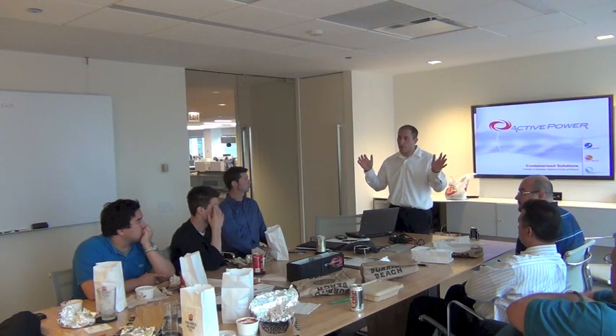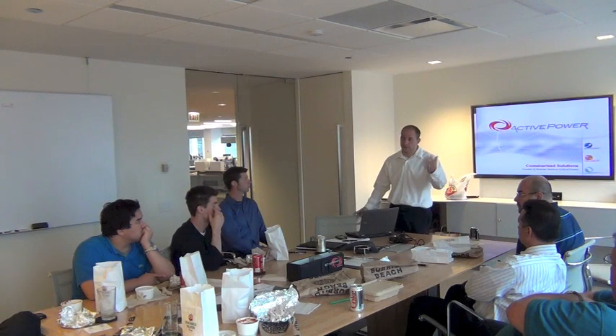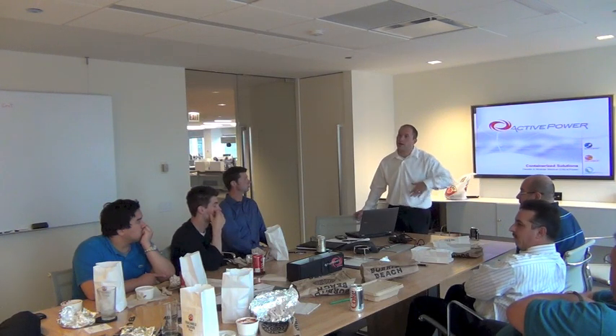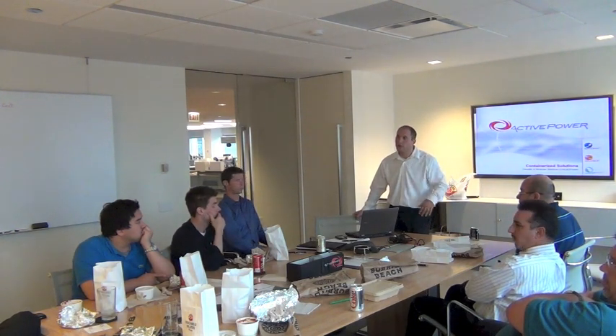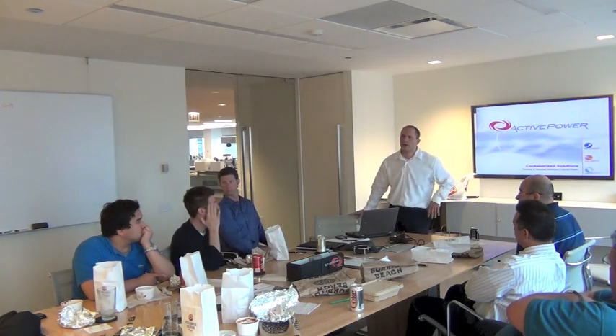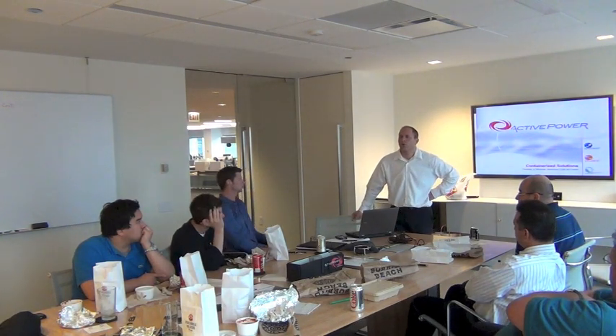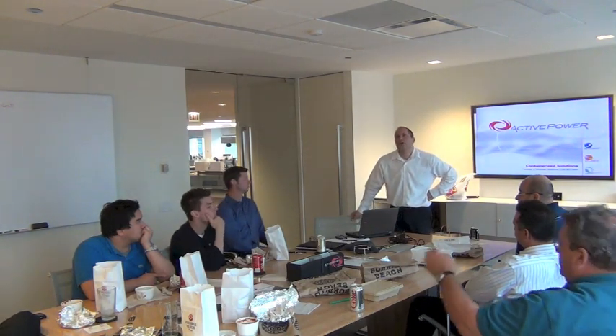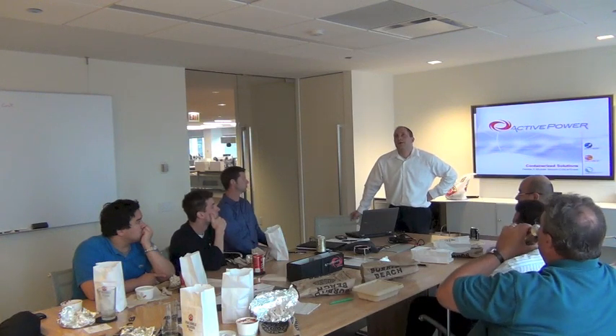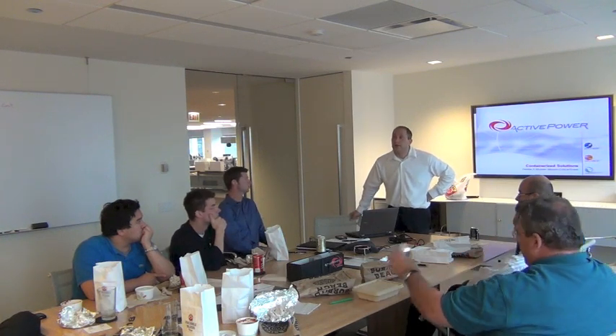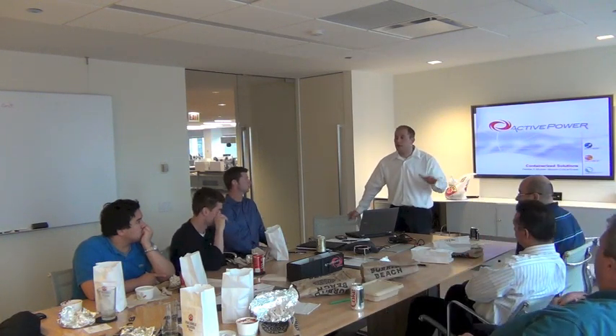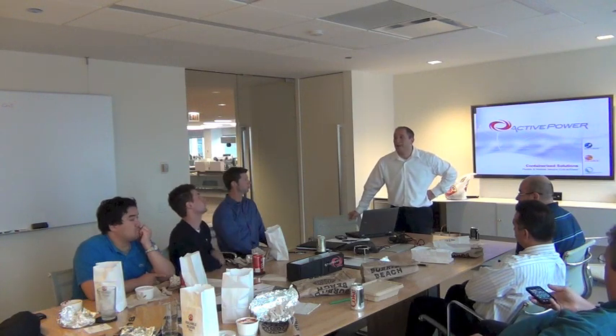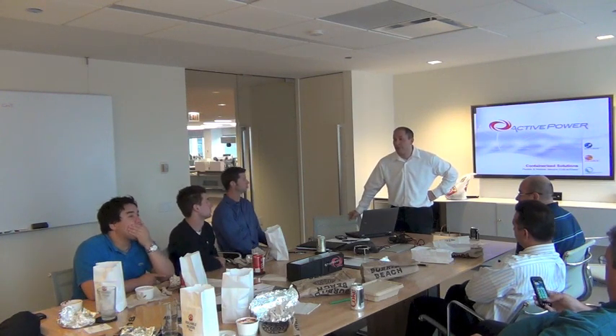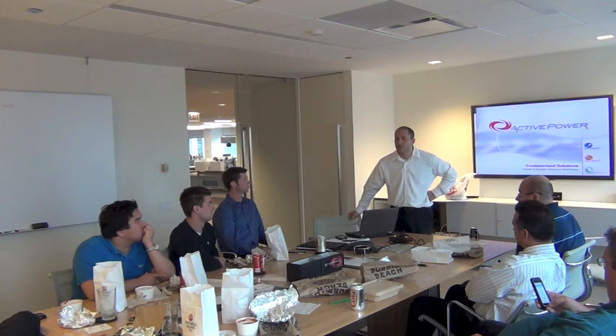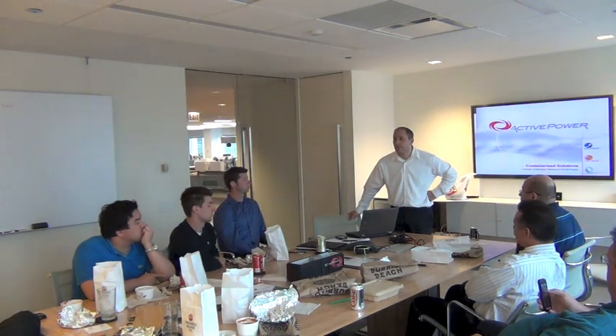And now you're going to be on generator, your load's going to be protected by generator. The UPS is going to qualify that source, and it's going to start recharging the wheel, basically. It's going to automatically come back online without human interaction. Typically, once you transfer to generator, you have, I'm going to say, 90 seconds to come up to speed. After 90 seconds, your wheel should already be up to full speed after a walk-in. And even if you don't complete the walk-in, you maybe add an extra 20, 30 seconds to that.